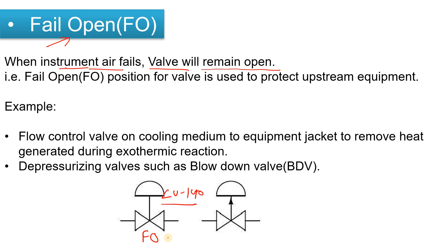What I want to say is, let's suppose there is an instrument air failure in the entire plant, and let's suppose there is an emergency shutdown, or there could be any reason to trip the plant. At that time, let's suppose this is one control valve, LV140, and in the P&ID you see that FO is written. What is the meaning of it? It means that when the instrument air fails, this control valve remains open. So the fail open position for a valve is used to protect upstream equipment.